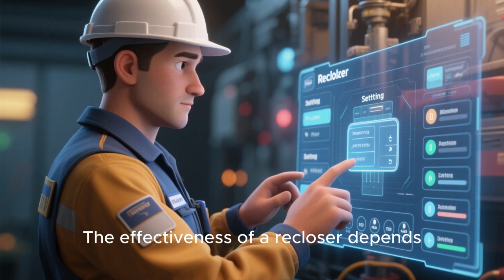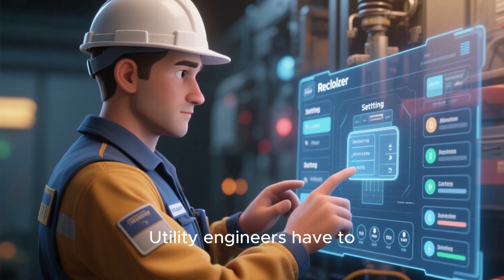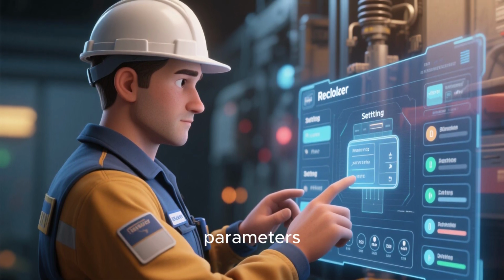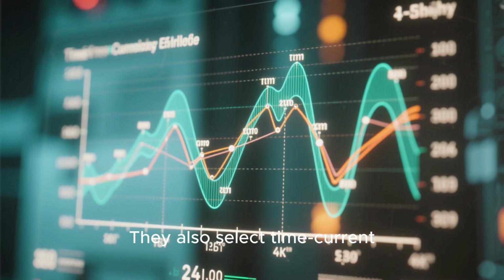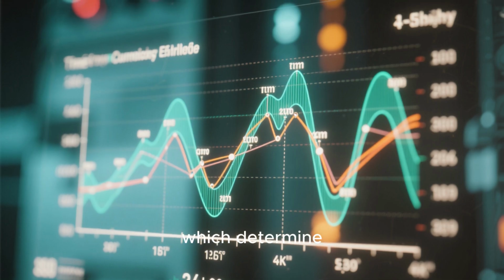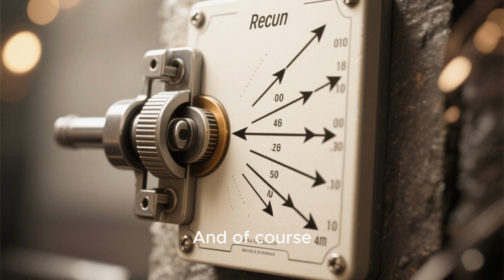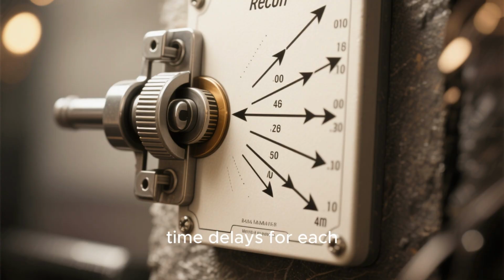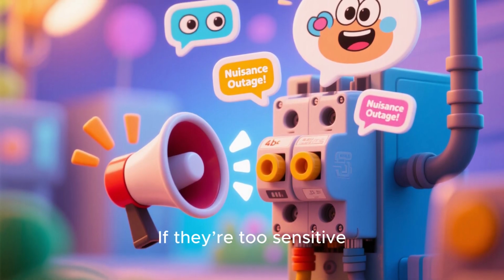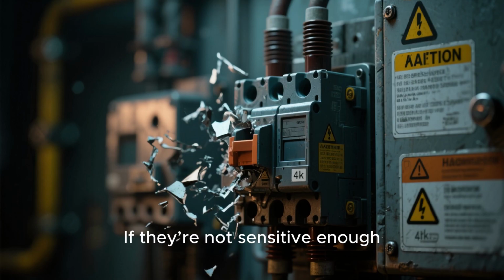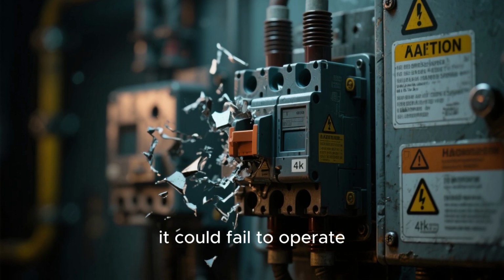The effectiveness of a recloser depends entirely on its settings. Utility engineers have to carefully program several parameters. This includes the pickup current, which is the level of current that signals a fault. They also select time current characteristic curves, which determine how quickly the recloser trips based on how high the fault current is. And of course, they program the reclosing sequence, the number of attempts, and the time delays for each. Incorrect settings are a big problem. If they're too sensitive, the recloser might trip unnecessarily, causing nuisance outages. If they're not sensitive enough, it could fail to operate, leading to equipment damage or safety hazards.